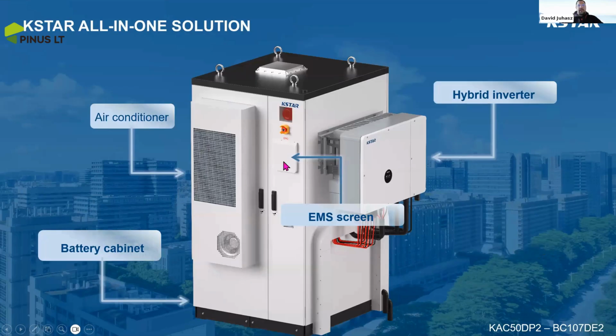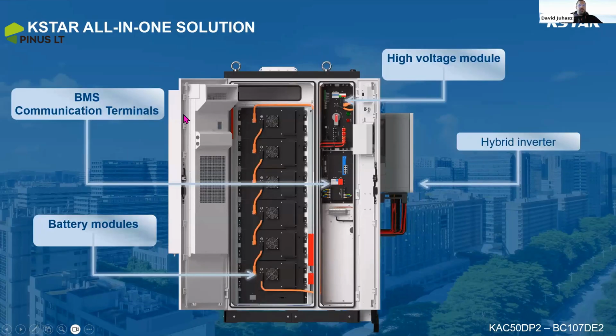So this is the all-in-one solution. We see the EMS LCD screen in the middle. This is the heart of the equipment, and the first commissioning is done here. There is an efficient air conditioner on the door, which automatically heats or cools the batteries inside according to the measured temperature. And we can see on the next page, when we open the door, there is a BMS communication terminal, the high voltage box for the protections of the AC and DC side, and of course the battery modules, which are in the column in the middle.